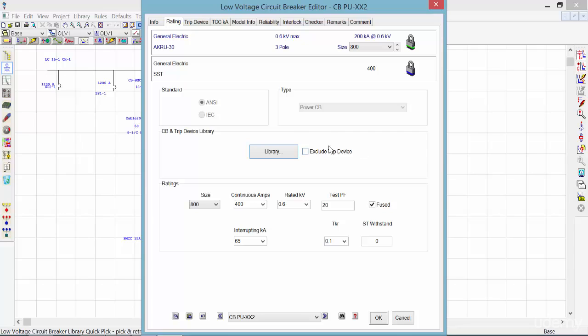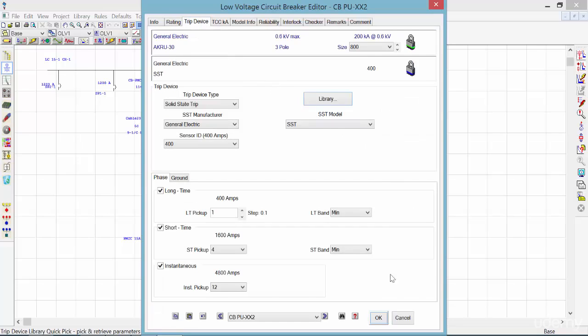So what we did, as you remember, is we chose from the library the solid state trip breaker from General Electric brand that can support the 800 amp frame breaker with the setting of 400 amp trip. What we're gonna do next is switch over to the trip device. In this window we can see the actual setting of the solid state breaker that we already picked. It has the type of the breaker, of course, solid state trip. The brand or manufacturer is General Electric. Its sensor is set at 400 amps.